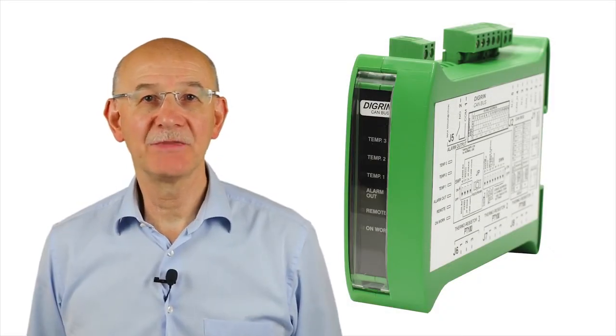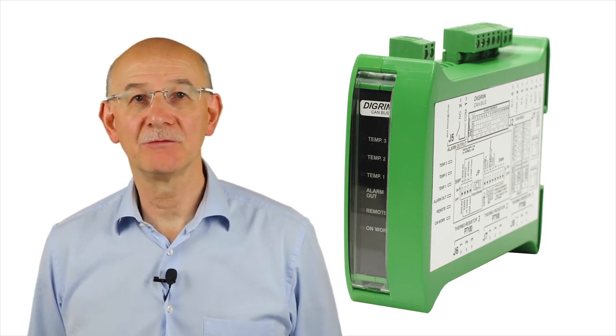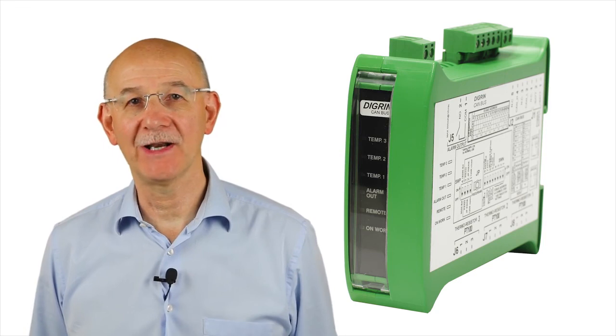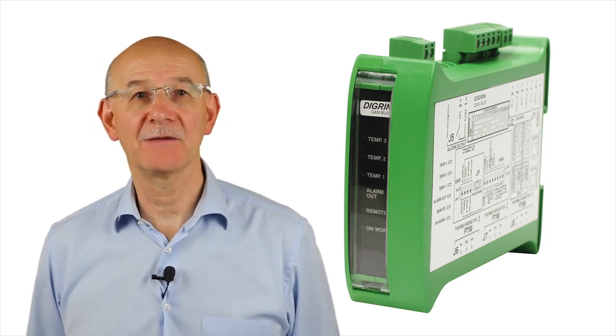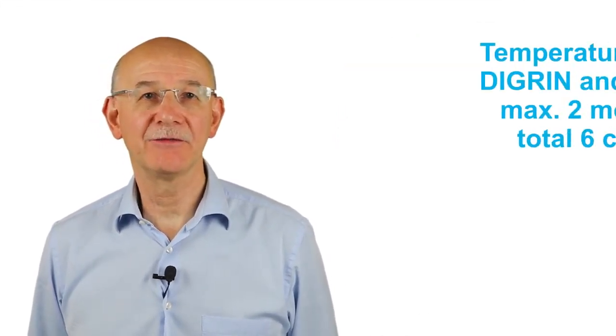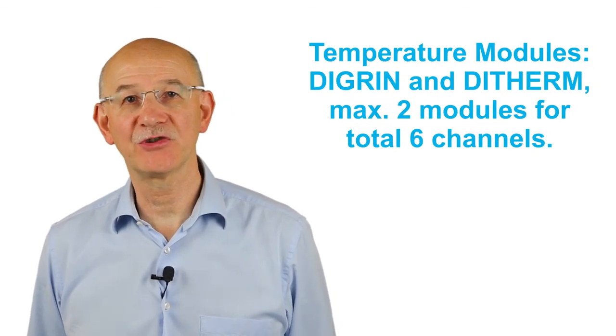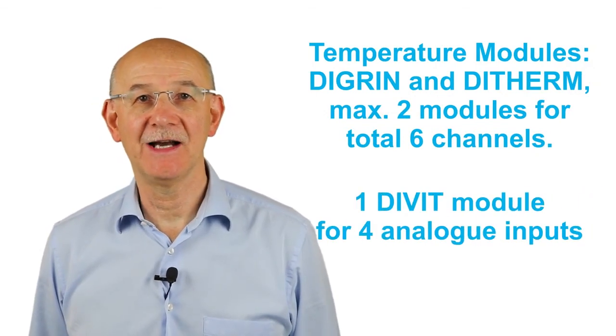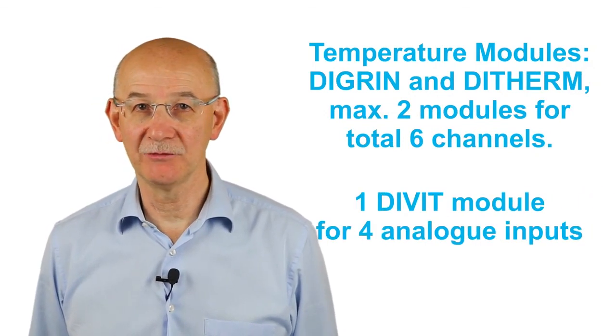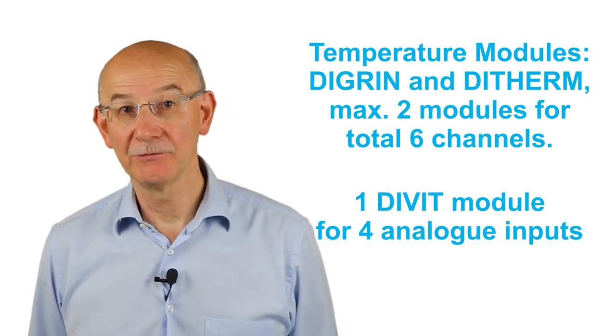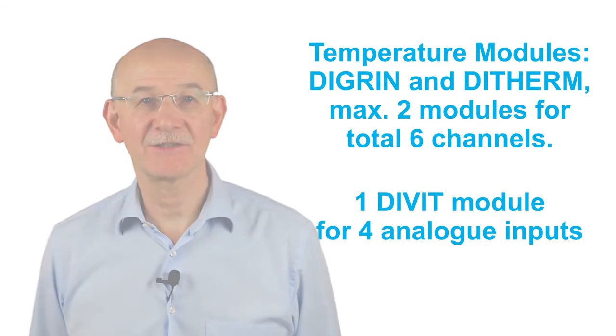Analog inputs can be expanded by external modules. Up to 2 temperature modules, DIGRIN for PT100 or DITHERM for thermocouple, can be added for a total of 6 temperature channels. An additional analog voltage/current input module can be added too, for a total of 4 channels.